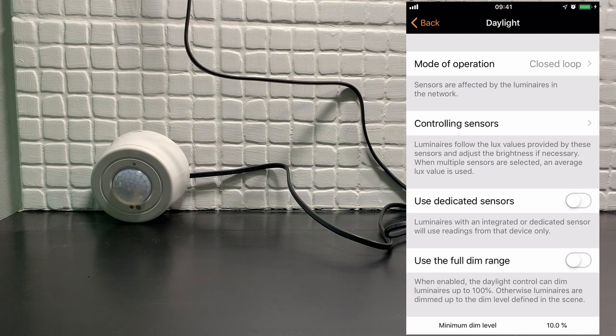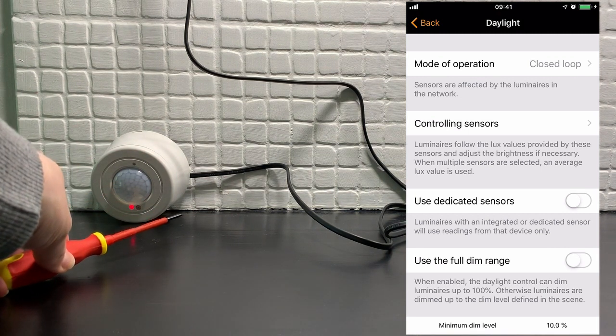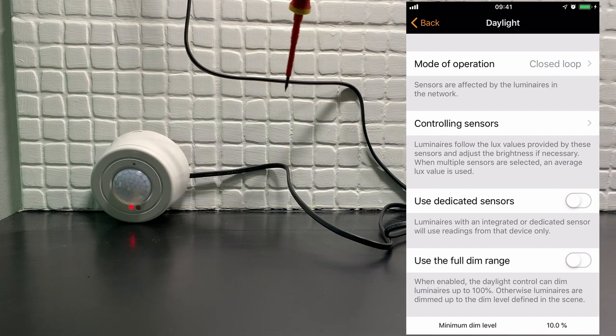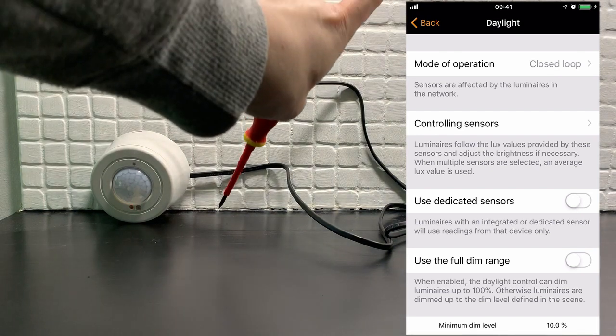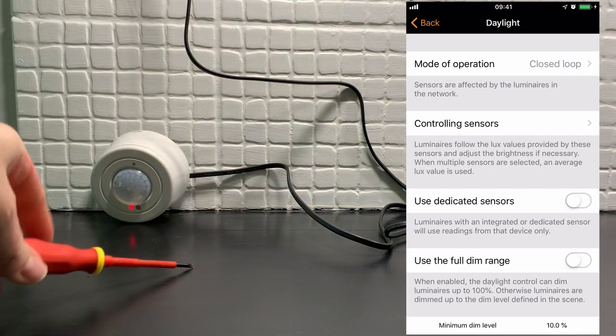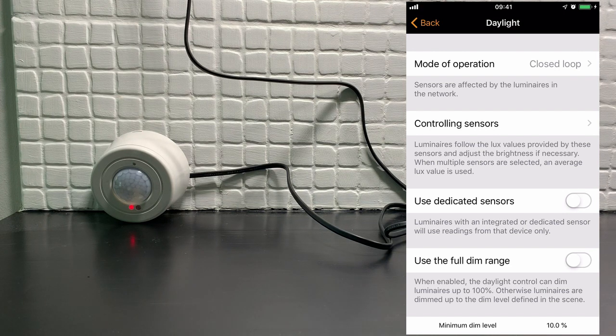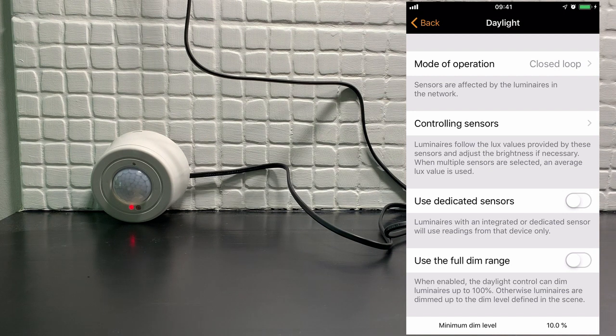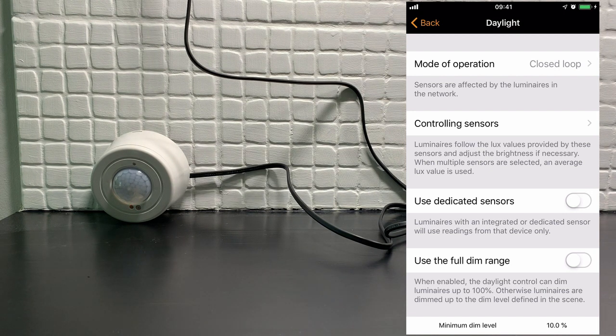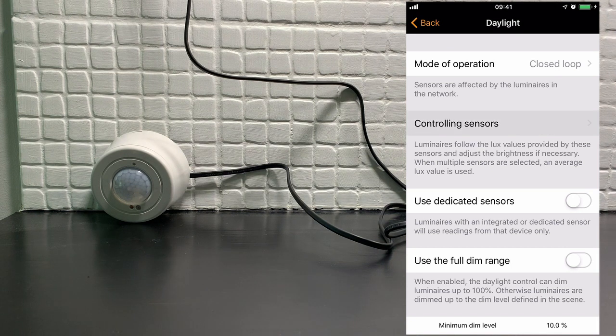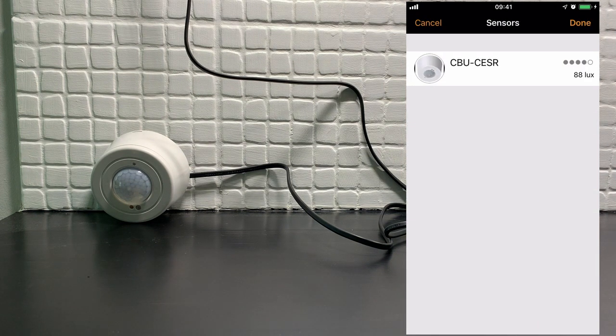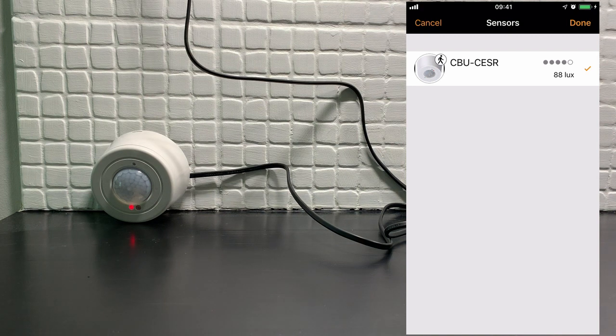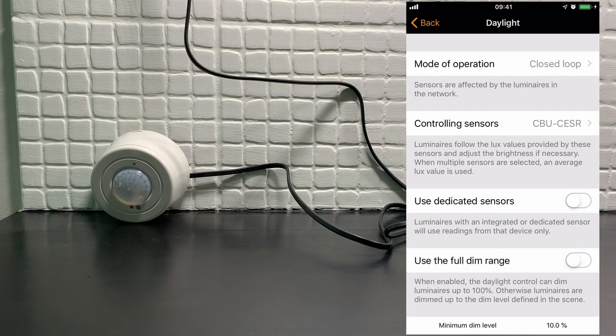But for this particular demonstration, we're going to use the closed-loop. The reason for that is we have our sensor here and the luminaires are above us. So we have selected closed-loop as our mode of operation. We now need to select a controlling sensor. In this case, we only have one sensor, but you could select multiple sensors and the value would then be averaged across them all.